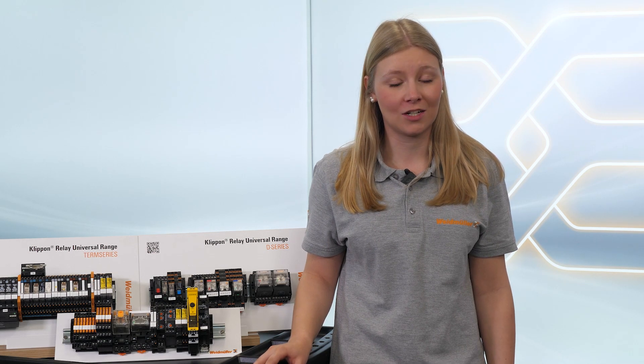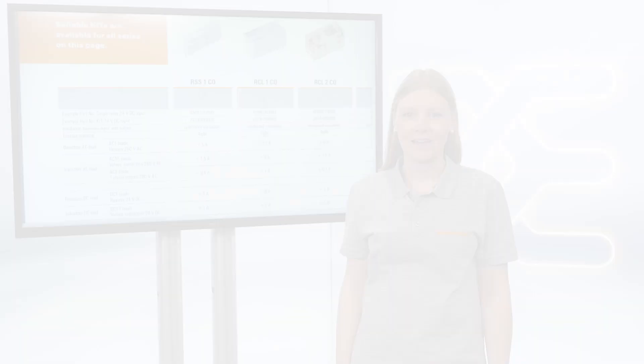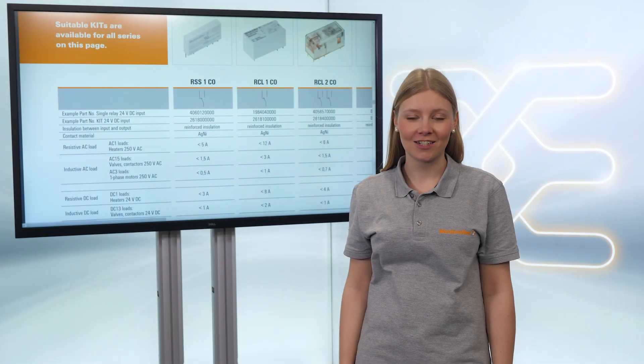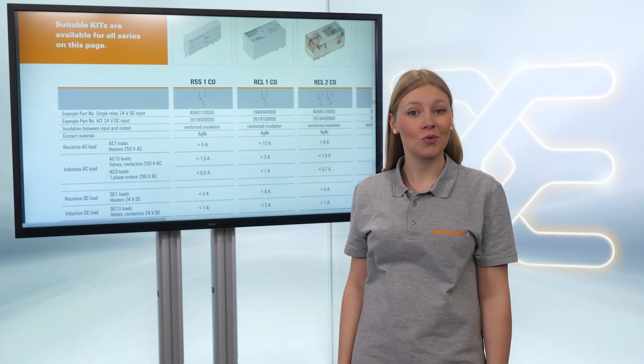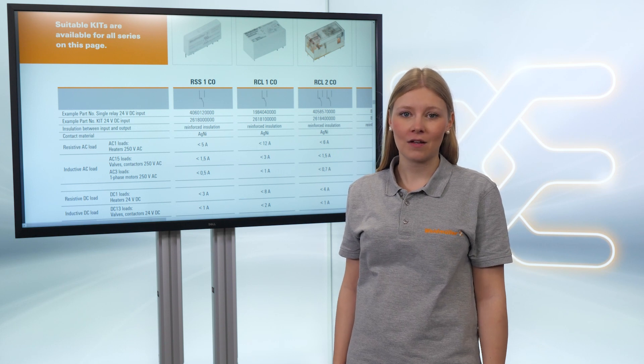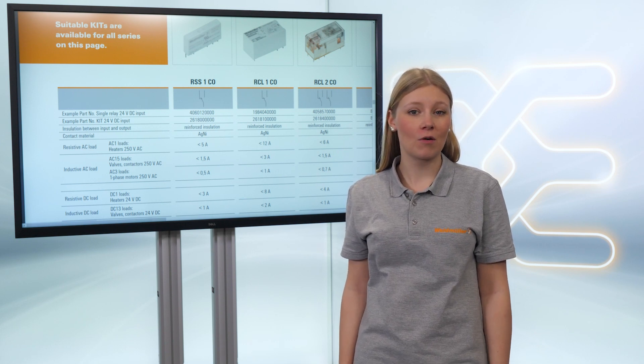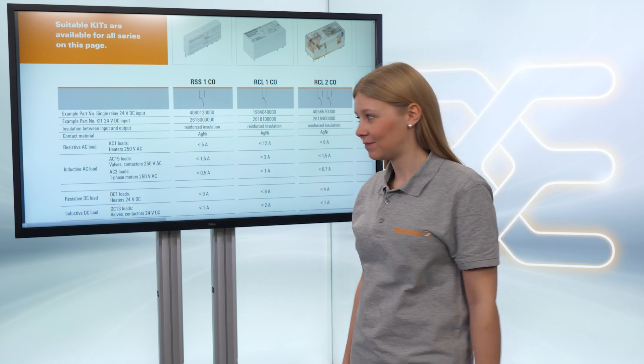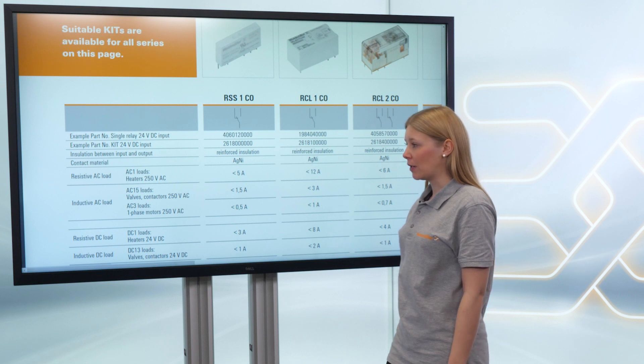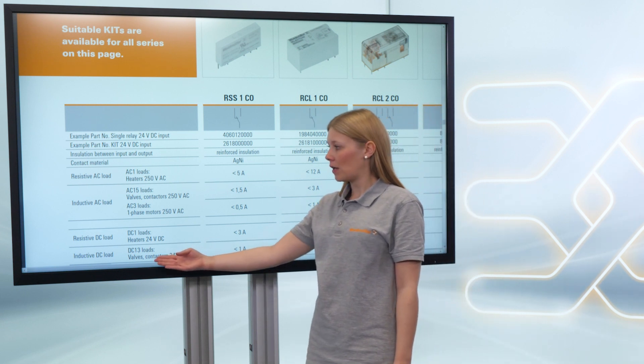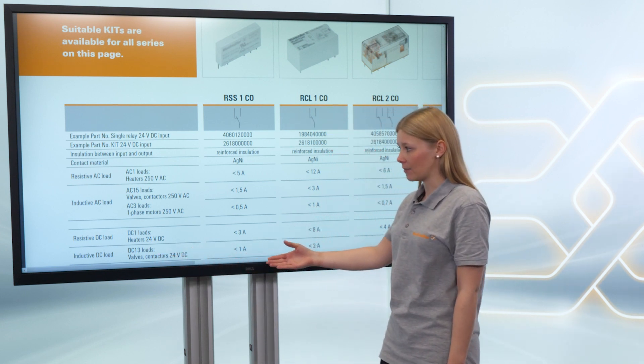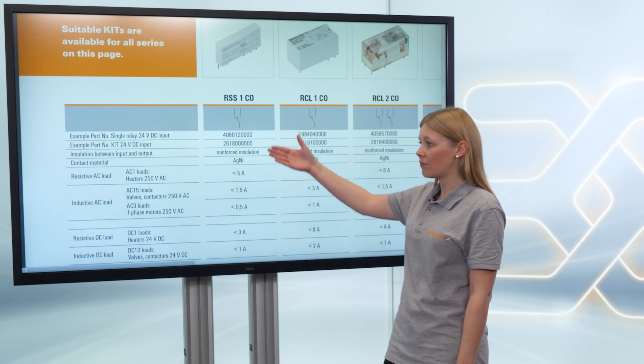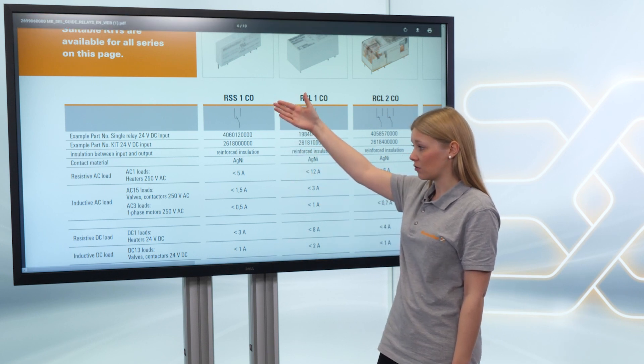Hey Weidmüller, do you have a solution for me to find the best relay for my application? In our brochure, the selection guide for electromechanical relay modules, we provide the customer information about the correct dimensioning. Let's take the lifetime as an example. I want to switch a 24 volt DC valve with 200 milliamps. In the table, I find the Term series as a one change-over.